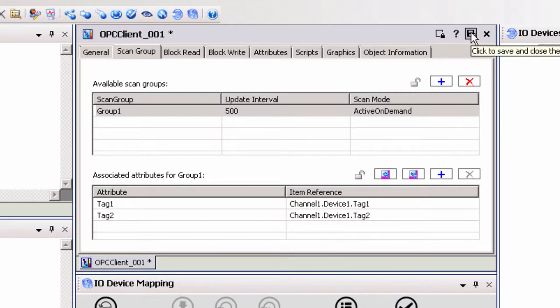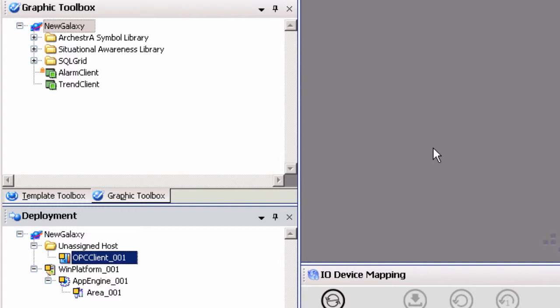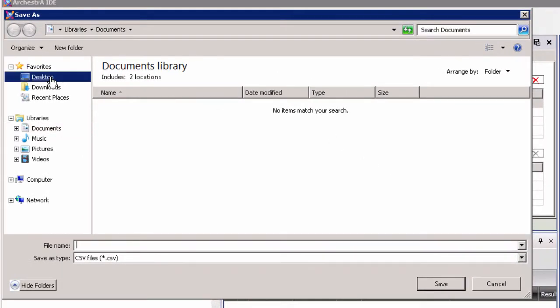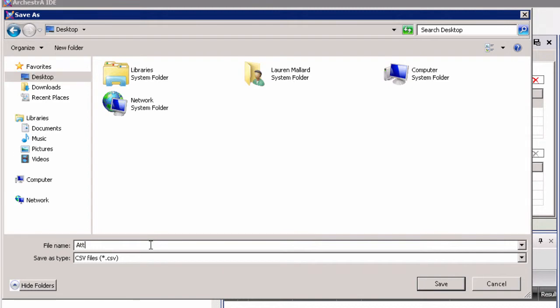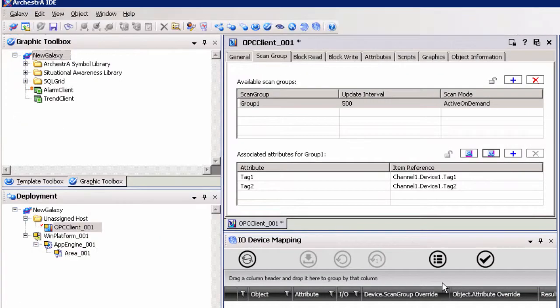Save and close the OPC client object to submit these changes. You will be prompted to check in the changes made. If you will need to add many items to your System Platform project, manually creating or browsing for OPC items may not be the most efficient method of configuration. System Platform also supports importing CSV files into the scan group attributes list for the OPC client object. In order to determine the format System Platform expects for the CSV file, it is helpful to create one item manually and perform a CSV export. Since we already have items configured in our attributes list, we can go ahead and export the CSV file by clicking the export button next to the attributes list. Once the file is saved, you can open it to see your configured items in the format used by System Platform. The first column represents the attribute name and the second column represents the item reference.